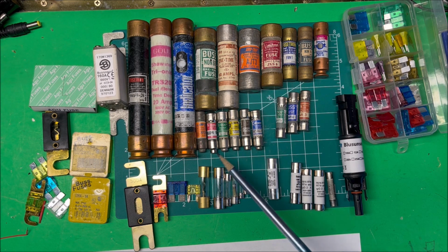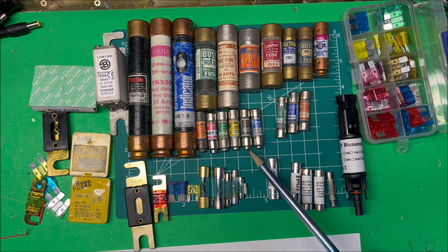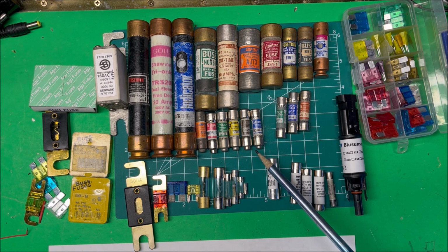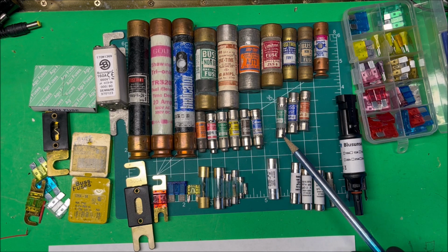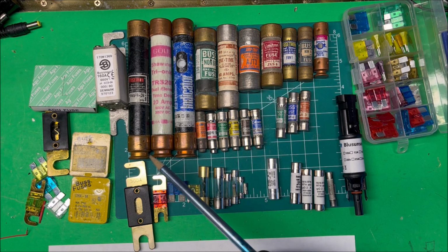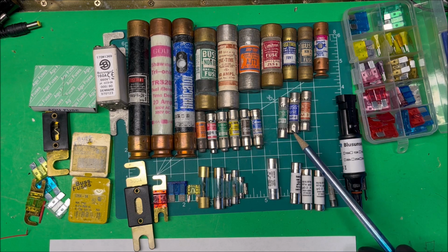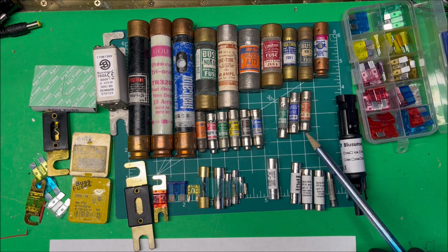Now they have these little knobs on the bottom because the 600 volt fuse holders they go into have rejection clips on them, so you can't put one of these fuses in this clip over here. Same with these, they have rejection clips on them. So this one's a time delay fuse, and then these are normal fuses here, and they're for 240 volt. Okay, 250 volts there.